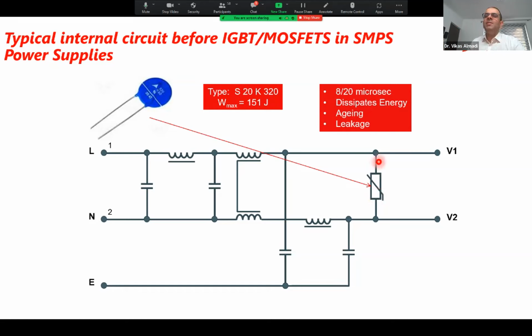And then every time there is a leakage of current, some microampere, which can go up to milliampere and maybe higher. You know that in your lines you are also using LAs. An LA is a big MOV, you can say. They have leakage, and you monitor the leakage to check whether the LA is still healthy or not. But inside the power supply, nobody checks it, and nobody can check it. And when it is exposed to surges or lightning much higher than the energy it can dissipate, it bursts, and that is what actually creates most of the failures.